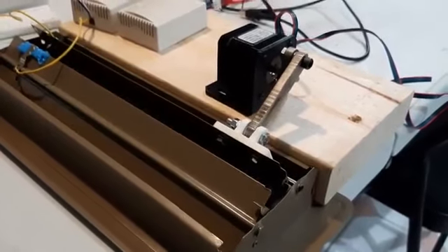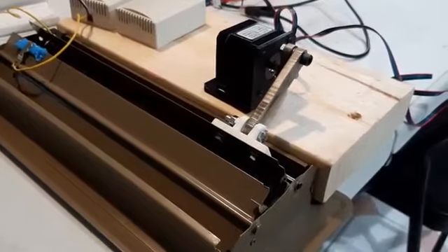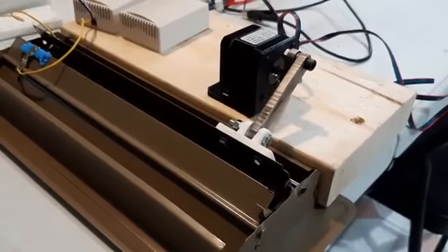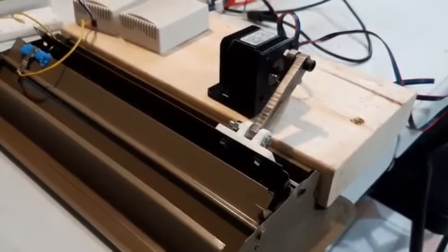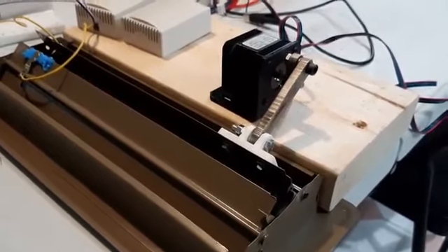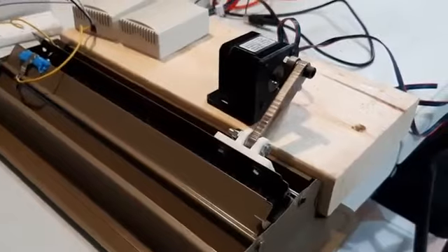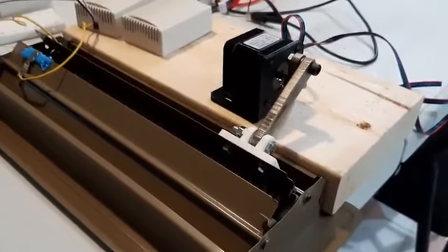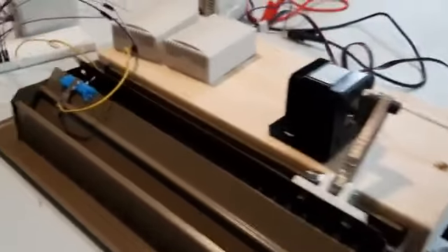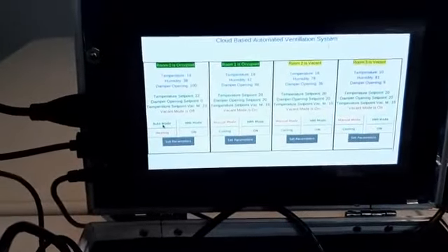Okay, you see it's more opened, and it opens until it reaches the maximum of 100%, and it cannot go beyond 100%. But, as I told, there is no airflow. Okay, and you see now the damper opening is 100%.